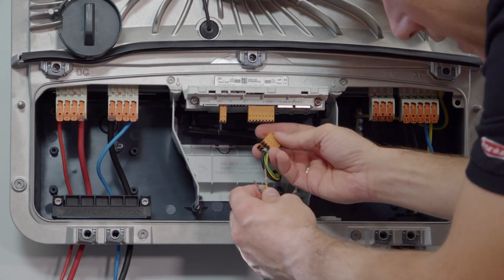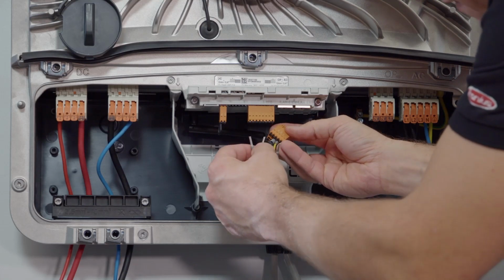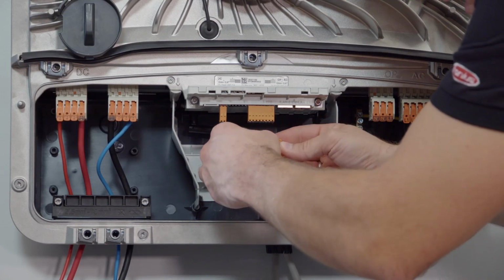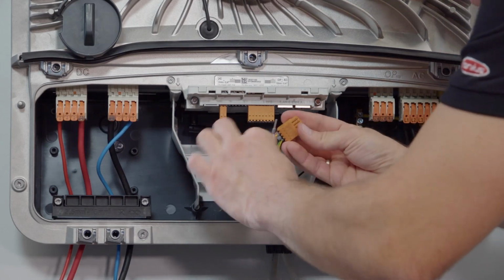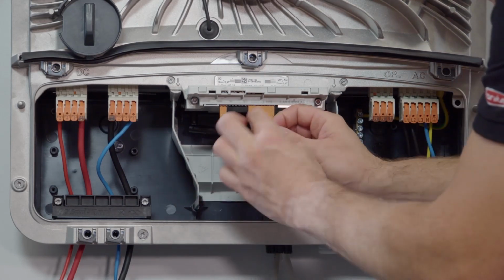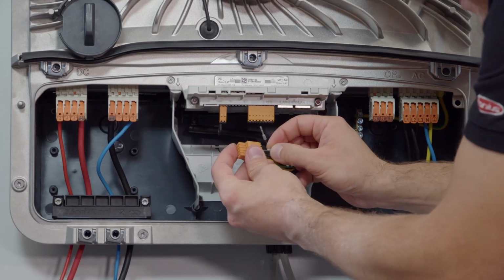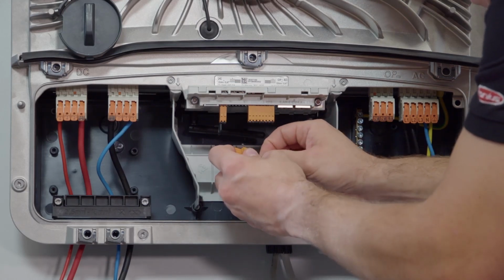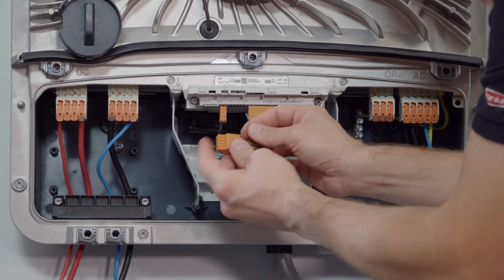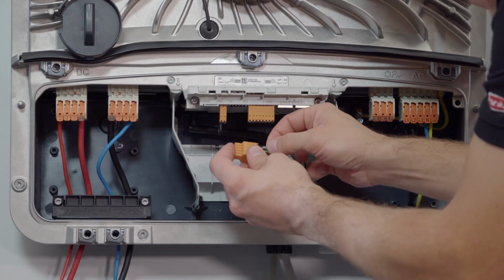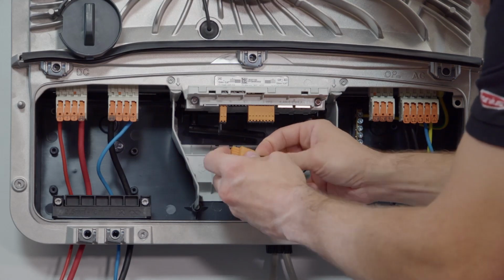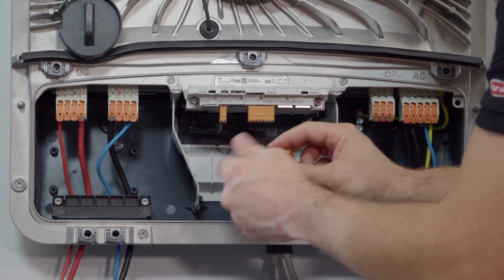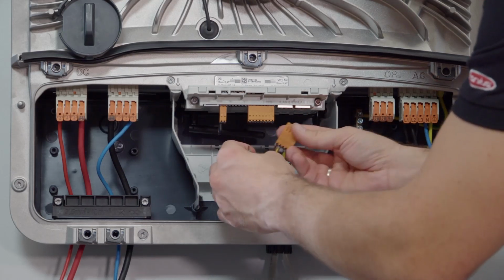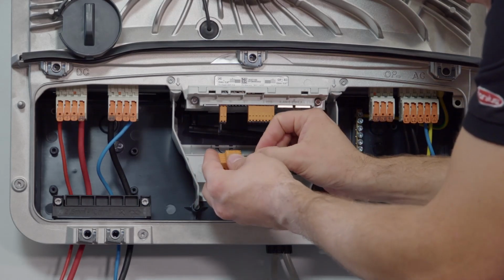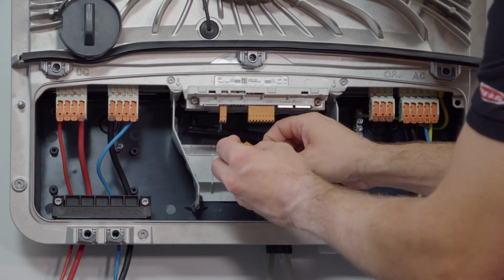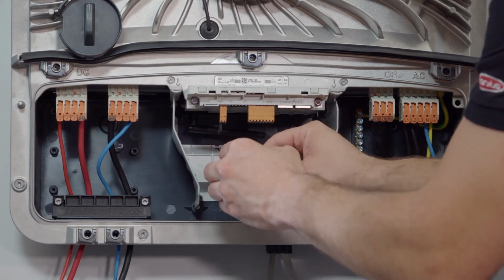the M0 Plus, and therefore we are going to start here with the yellow cable, with the yellow pin, into the M0 Plus. And on the other hand side, when we turn around the plug, we have here the M0 minus, and therefore we are going to install the second pin into the M0 minus. Last but not least, we have our ground connection, and therefore we are going to ground at the last pin. So the third pin goes into ground. And really important, again, now we need the shield contactor, and we can bring the shielding of the cable directly here to our shield contactor at the GEN24 Plus data communication interface.